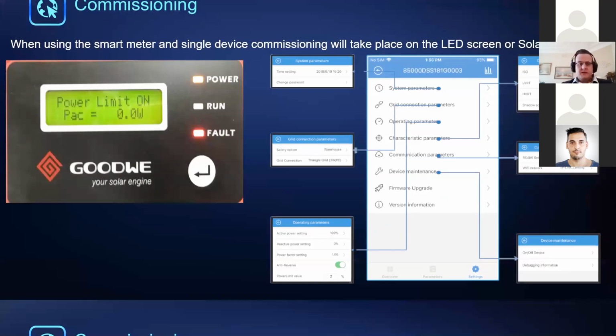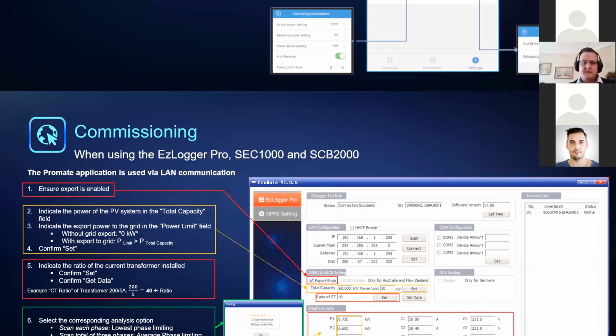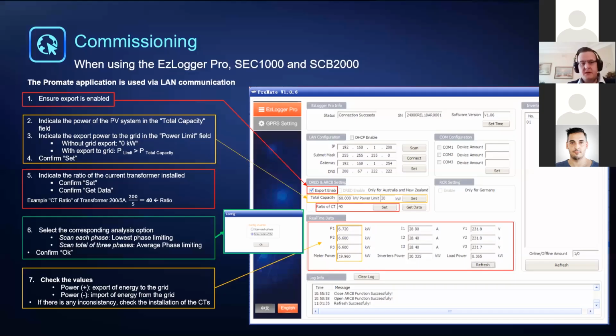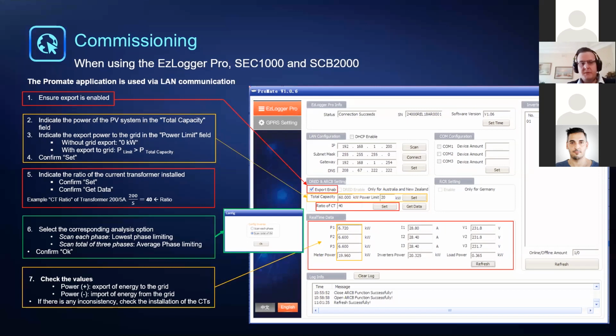Commissioning when we use the EZ-Logger Pro, SEC 1000 and SCB 2000, we use an application called ProMate, and this works over LAN. So we connect to the device. You can either connect directly with a laptop or connect it to your local network, scan for its address, and then connect to it. Yes, there are some important things we need to pay attention to when we set it up with ProMate.